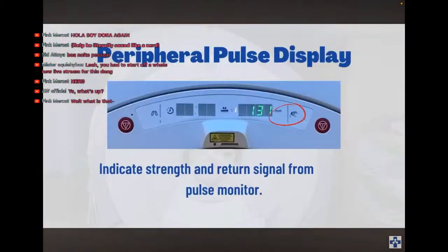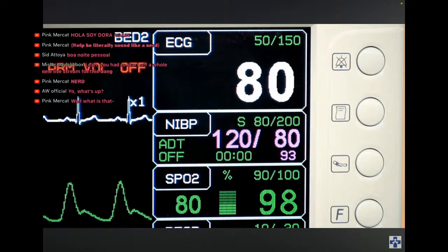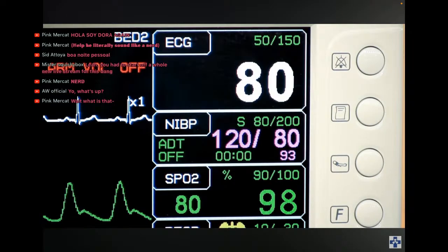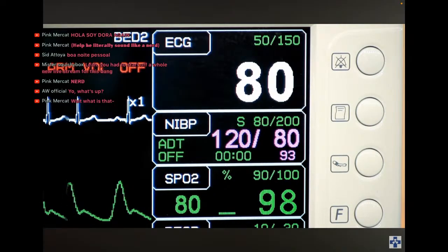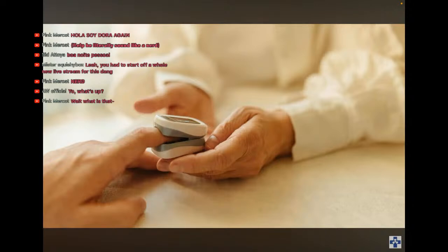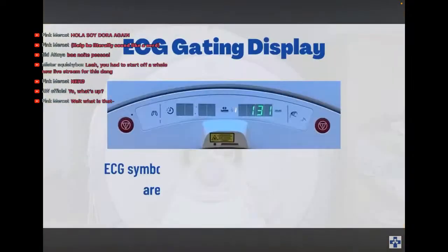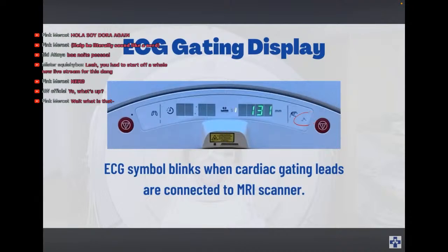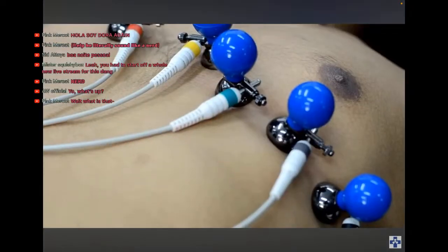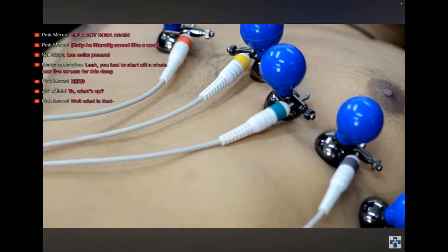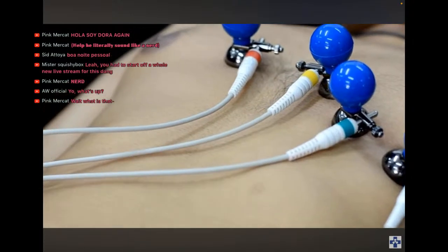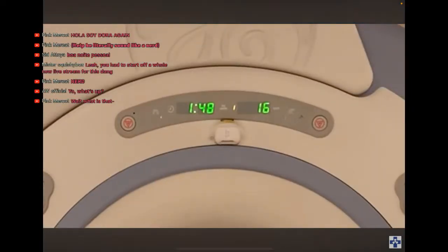Next to the patient location status, we see another bar graph LED similar to the respiratory bellows status display. This LED displays strength and return signal for the peripheral pulse monitor. The pulse sensor is placed around the patient's finger to monitor heart rate during the MRI scan. The last LED indicator is the ECG lead display. This simple LED indicates strength and return signal of the cardiac gating leads. It blinks when electrocardiogram leads are...